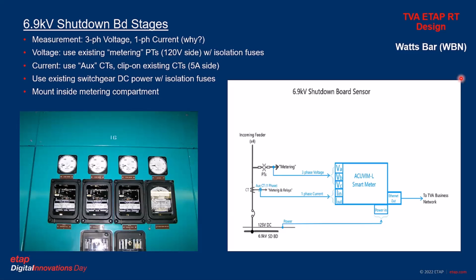To be as non-intrusive as possible, we'll be using isolation fuses for connecting the PTs. Therefore, we won't jeopardize any operating plant equipment. And we're going to use auxiliary CTs, which are a clip-on type CT. You can think of it as like a one-to-one CT, which is also very non-intrusive, very low mass. And we will use our existing switchgear DC power supply with isolation fuses to power the smart meters. And the smart meters will be mounted inside the metering compartment, so we don't have to cut holes through the door or anything like that.